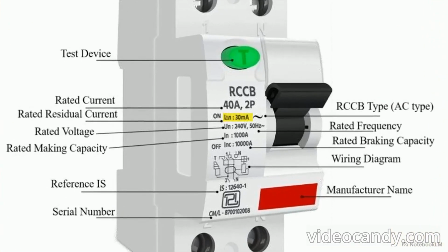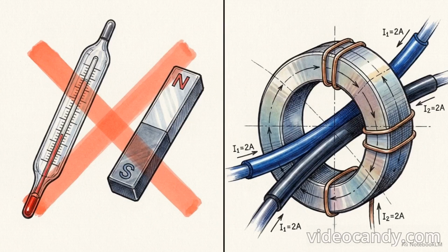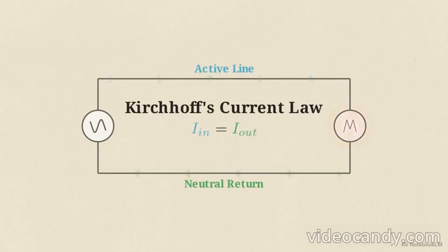Notice the print on the housing. It has a rated sensitivity of just 30 milliamps. The RCCB achieves this by abandoning heat and magnetism entirely. It operates exclusively on differential current monitoring. The logic relies on Kirchhoff's current law. In any closed loop, the exact amount of current entering the circuit on the active line must equal the amount of current leaving the circuit on the neutral return.